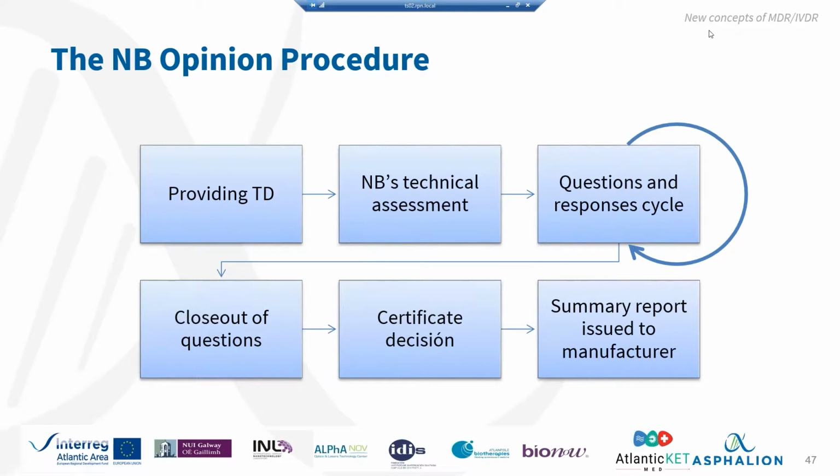Okay. So how does this notified body opinion procedure work? How is this obtained? First, you've got to provide the technical documentation of the device to the notified body. This notified body will perform a technical assessment of the documentation you have sent, and they might ask back for more information if it's not there.